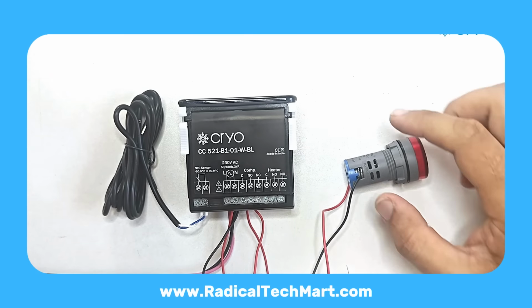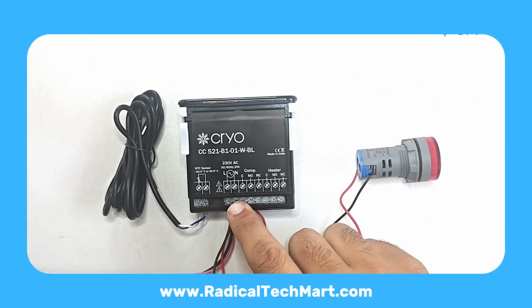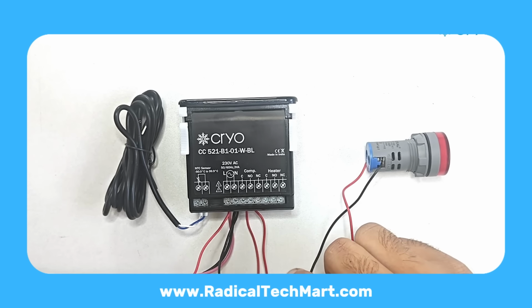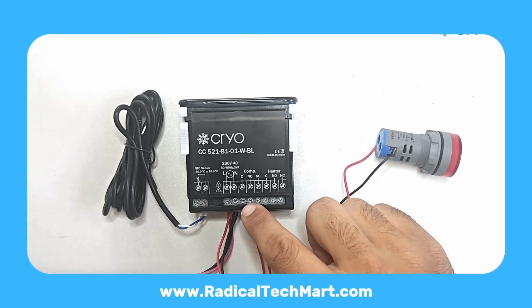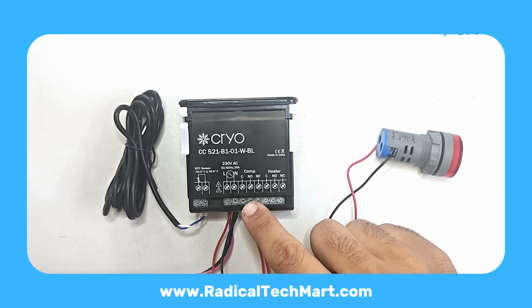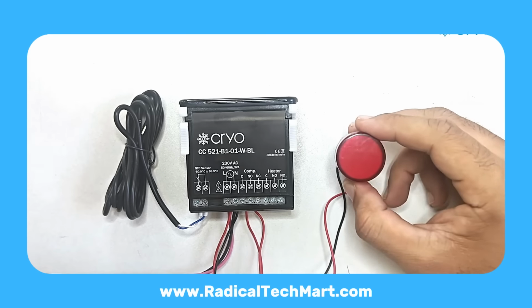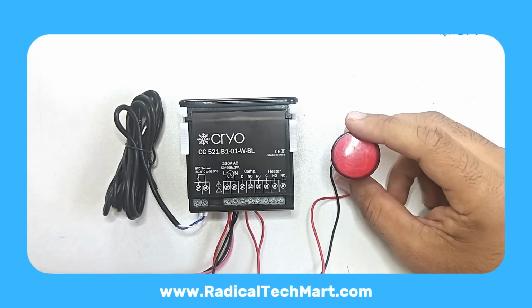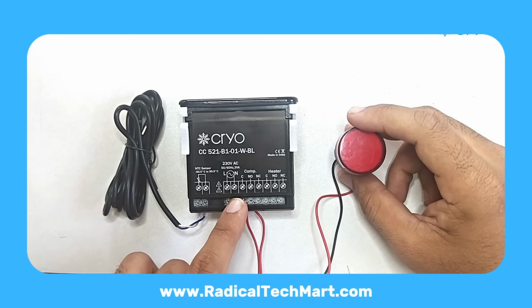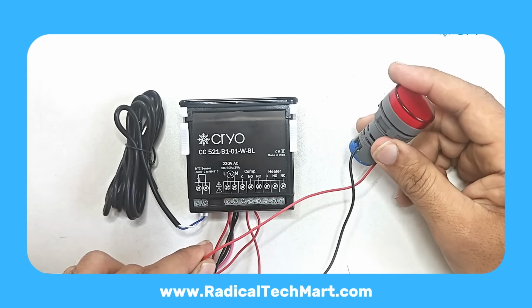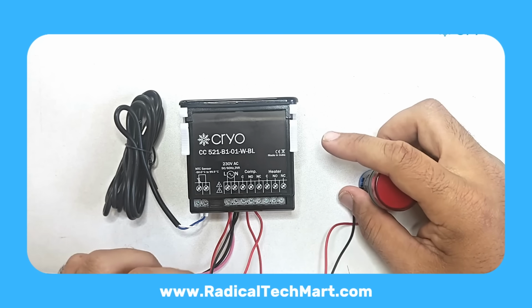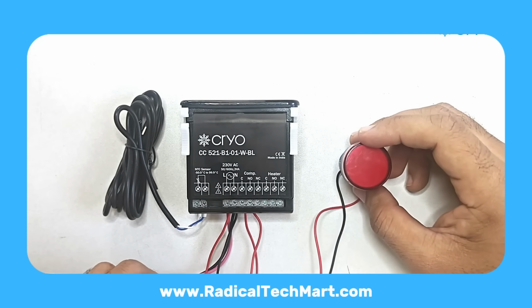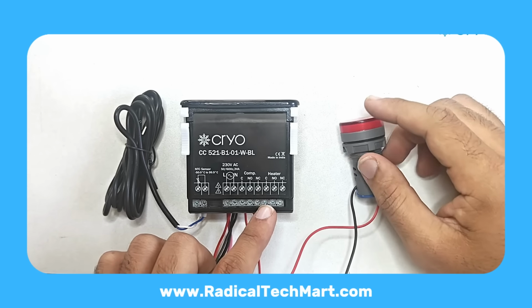For wiring, connect the line and neutral to L and N. Loop one wire from line, L, to the common, C, of the first relay. This relay will control the compressor. From the NO, normally open, terminal, take an output to the compressor, or in our demo, to an LED. So whenever the LED turns on, the relay output is active.